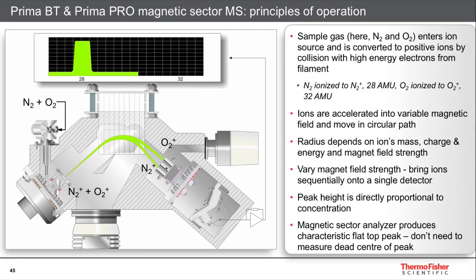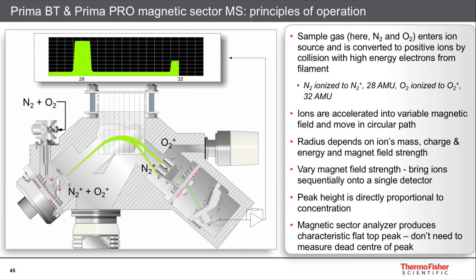This is a magnetic sector mass spectrometer operating on the principle of a scanning electromagnet. Like most mass spectrometers, it consists of three main components: first, the sample is introduced into an electron impact ion source, where electrons produced by a filament impact neutral molecules to produce positively charged ions. Second, those ions are accelerated into a scanning magnetic field — the radius of an ion through a magnetic field is a function of its mass, charge, and magnetic field strength, allowing selection of ions of a given mass to pass into the detector.